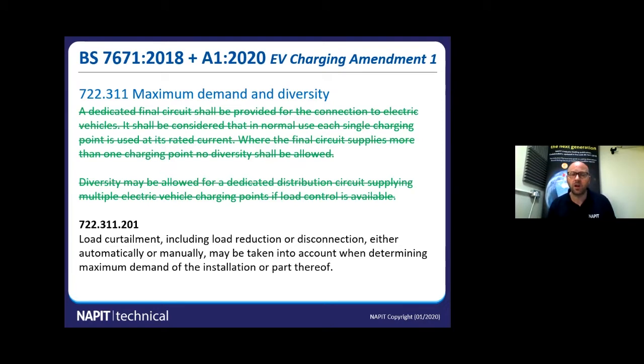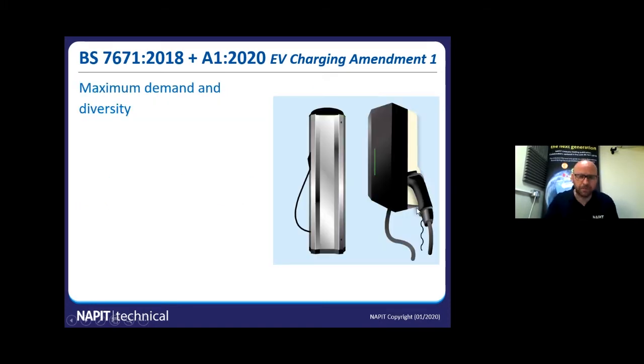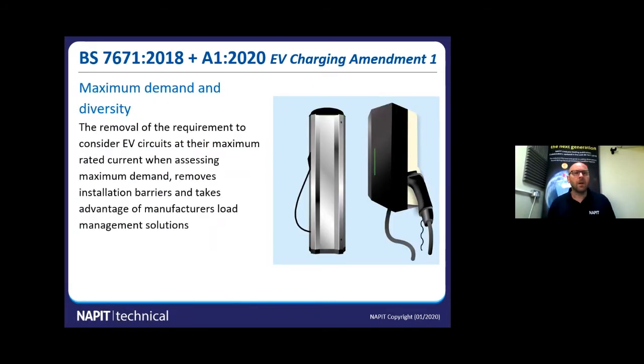So the new regulation in the amendment, written at the bottom there, 722.311.201, allows for load curtailment, including load reduction or disconnection. It can be either automatic or manual, and it must be taken into account when determining the maximum demand of an installation. So it gives us some solutions. The removal of the requirement to consider EV charging points at the maximum rated current removes installation barriers, as I've previously said. It takes advantage of the manufacturer's load management solution. So I'm just going to hand over to Conor, who's going to talk about their dynamic load management system.